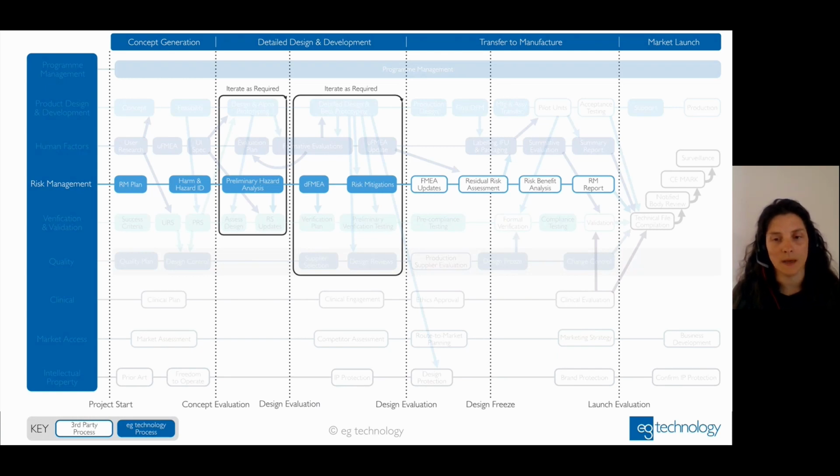And it's important this is done by suitable people with the relevant knowledge and expertise, typically the relevant clinical expertise, in order to really assess whether the benefits suitably outweigh the risks for your product. And this all gets compiled into a risk management report at the end.